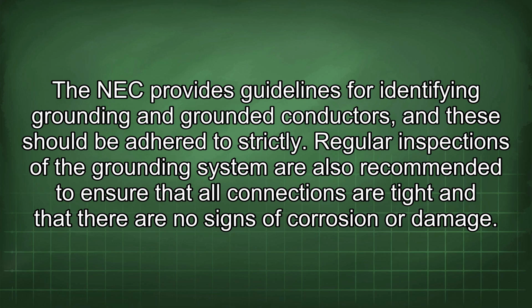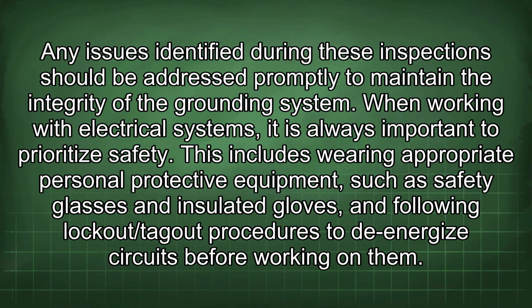Regular inspections of the grounding system are also recommended to ensure that all connections are tight and that there are no signs of corrosion or damage. Any issues identified during these inspections should be addressed promptly to maintain the integrity of the grounding system. When working with electrical systems, it is always important to prioritize safety. This includes wearing appropriate personal protective equipment such as safety glasses and insulated gloves, and following lockout/tagout procedures to de-energize circuits before working on them.